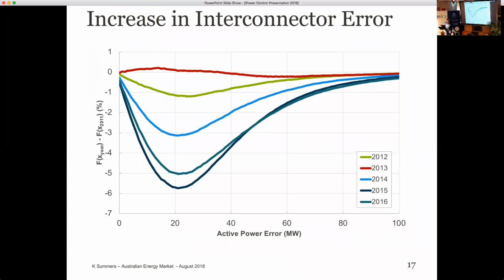We did some work on this. This has been updated, we've got an updated chart that I didn't get the chance to include here, but it's in a later paper coming out in the IET hopefully later in the year. This is the interconnector error to its target, showing accumulated error up to 6% of the time, about 5.8% of the time to 20 megawatts in 2015. There was a period where Basslink was in and out, and I think the 2015 period shows the worst case, but you can see it varies a little bit.